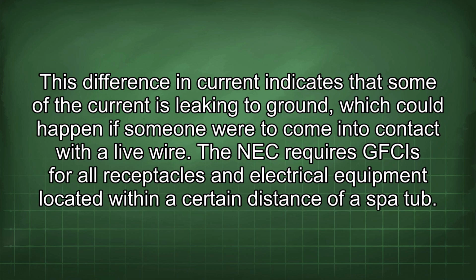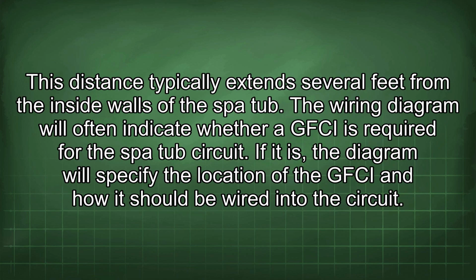This difference in current indicates that some of the current is leaking to ground, which could happen if someone were to come into contact with a live wire. The NEC requires GFCIs for all receptacles and electrical equipment located within a certain distance of a spa tub. This distance typically extends several feet from the inside walls of the spa tub. The wiring diagram will often indicate whether a GFCI is required for the spa tub circuit.